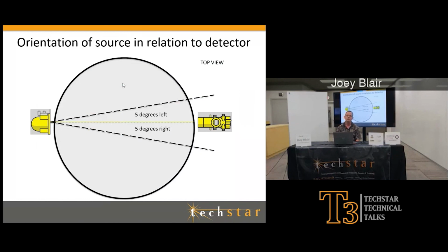The way that we check that in the field, again, is we use our handheld Geiger counter. We would install our source, and install our detector, or at least know where we wanted it. And then I would get my Geiger counter and I would move it throughout that area. And I would look at my radiation fields and I would see where my strongest field is. Or I would install my source holder, turn it on without my detector installed, find that strongest area, put an X on it so I know where I want to mount my detector, and mount it there.